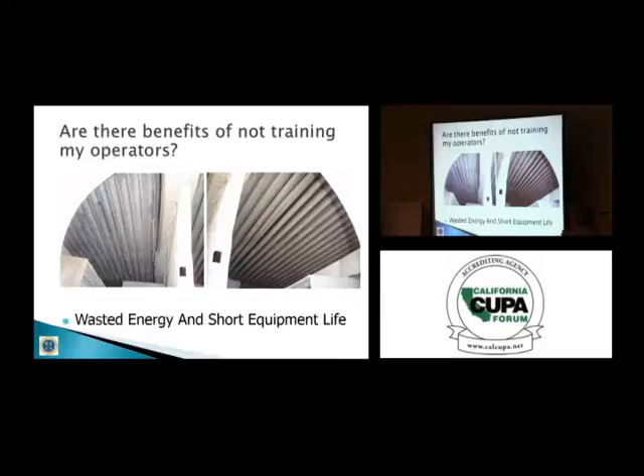This bundle here is not a coral reef. The irony of this is it's in the same box. So, again, I'm a practical engineer. What's going on here? Well, this one's not crudded up. Why? It wasn't seeing water. If it doesn't see the water, it's not doing a lot of work.